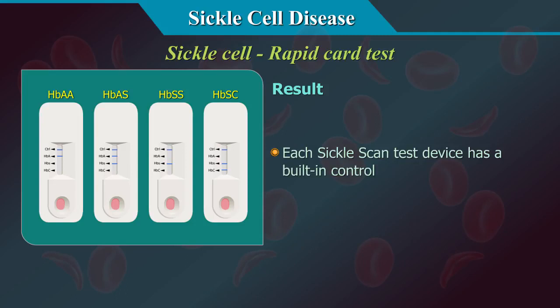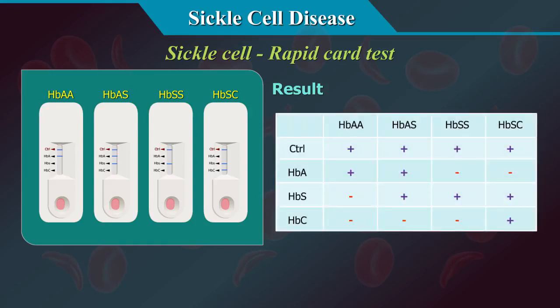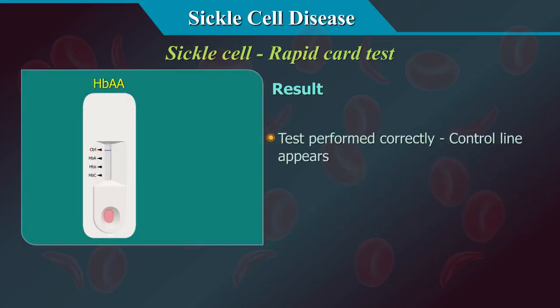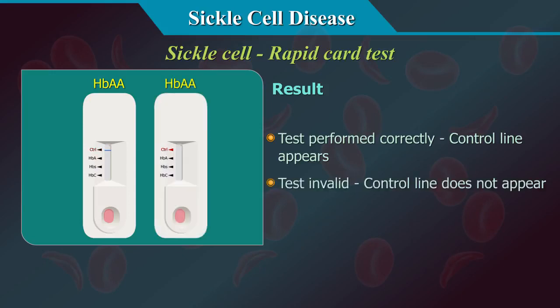Each sickle scan test device has a built-in control. A dark blue coloured line in the detection window at the control line position can be considered an internal positive procedural control. The control line will appear if the test procedure has been correctly performed. If the control line does not appear, the test is invalid and a new test must be performed. If the problem persists, please contact your local vendor.